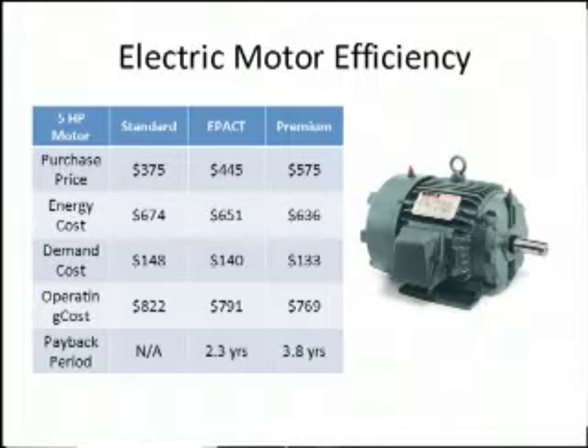Motor efficiency is another one that we've used a lot of at UCF, replacing a lot of units based on these savings numbers. So this is just for a 5 horsepower unit, a relatively small motor for us. We can get between a 2 and a 3 year payback, or 2 and a 4 year payback, depending on which unit. And I think we're mostly speccing the EPACT, which is the standard high efficiency motor, but we use some of the premium as well, depending on the horsepower. These efficiency ratings change quite a bit. So this is just applicable for a 5 horse. So I encourage you to look at whatever horsepower you're replacing, run those numbers and see what the payback really is. And don't forget to include both the consumption savings and the demand savings in your calculations, which is critical.